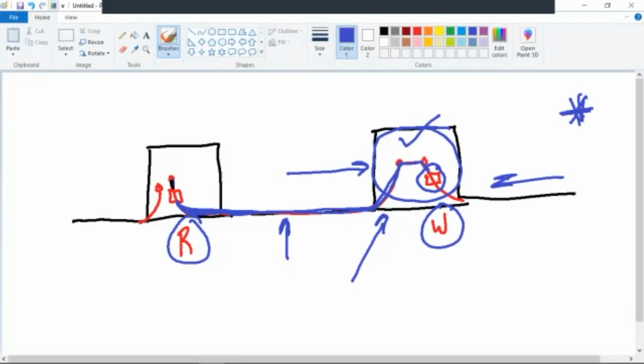Question real quick, Mr. Shoemaker. Yes, sir. If you had a dip pole in this picture right here on the left side of that transformer, and you had to switch on the pole, so that would technically monitor from the dip pole through that transformer to that fault indicator. Mm-hmm. So that would be the same concept. Yeah, think of this. It's not your typical. You're not going to find any company that's going to put a fault indicator, and they do hang on the line. You can put them on wire. They're not going to put a fault indicator right here at the bottom of the switch. The fuse is the indicator. Yes, sir. And that's what I was saying. If it'll still monitor that first transformer. That is correct, because the fuse. You're exactly correct. There's no more I can say.